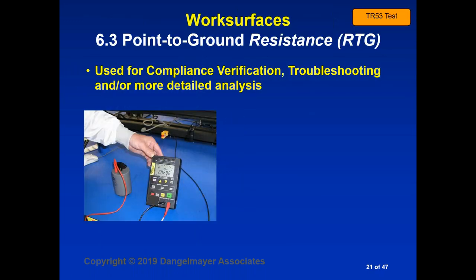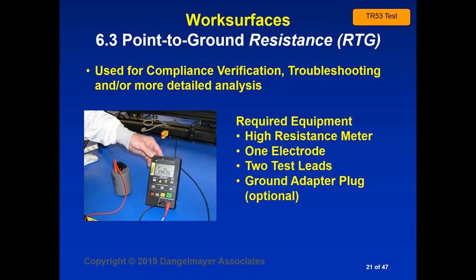So when you're doing compliance verification, you are almost always doing a point to ground measurement. It's a resistance to ground measurement. You're not measuring from point to point on the surface, but you're measuring from the surface to ground. These measurements are used for compliance verification. They're used for troubleshooting and some more detailed analysis if needed. So what you see here is a high resistance meter, one electrode, two test leads, and in the back there, I think you can see that ground adapter plug where you're making your connection to your AC ground.